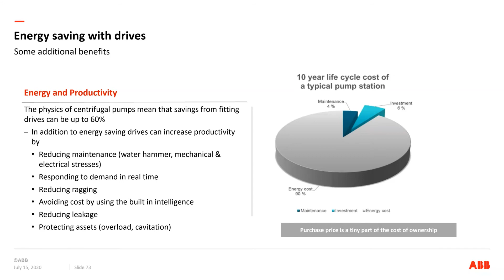A lot of other manufacturers have similar products, and they turn the impeller backwards to dislodge strings, debris, and buildup so it flows through the normal volutes inside the pumps. We're able to reduce maintenance on those pumps using the software and smarts of the drive. We're also increasing the flow, because as rags and debris build up on the pump impeller, it gets heavier and harder to turn, and less water can flow through. Using those features inside the drive really makes a substantial difference.